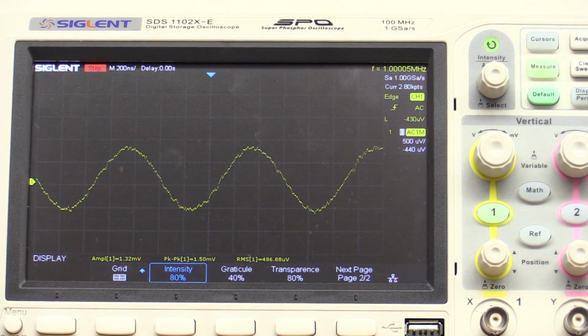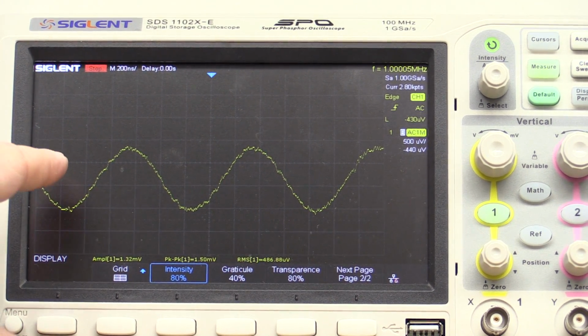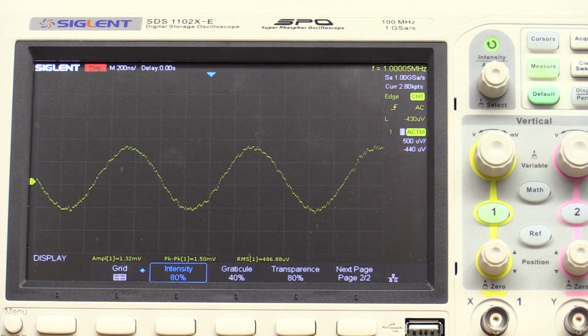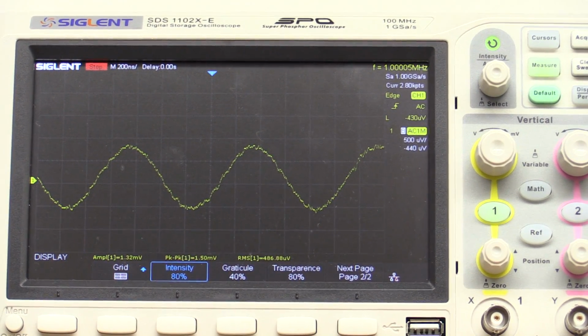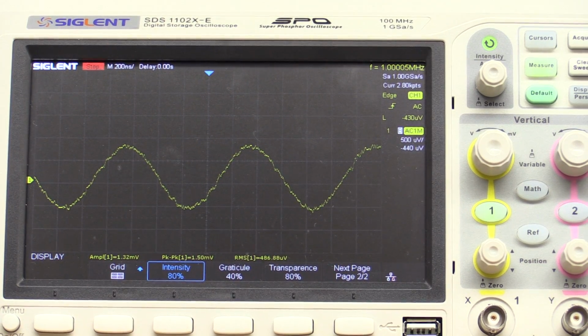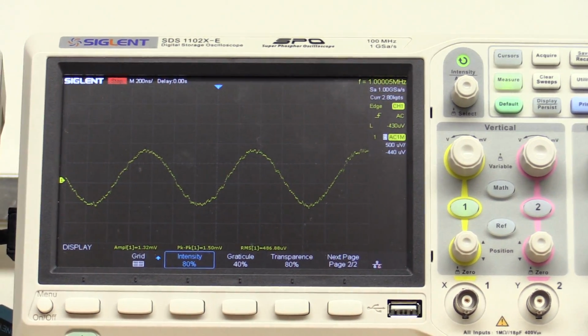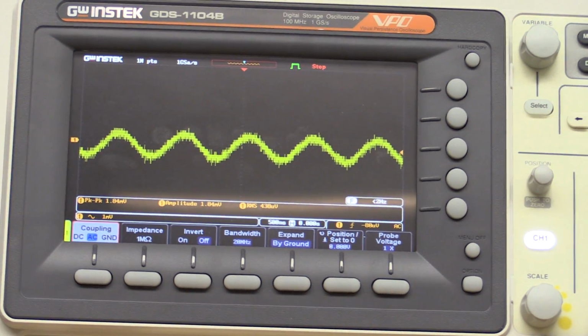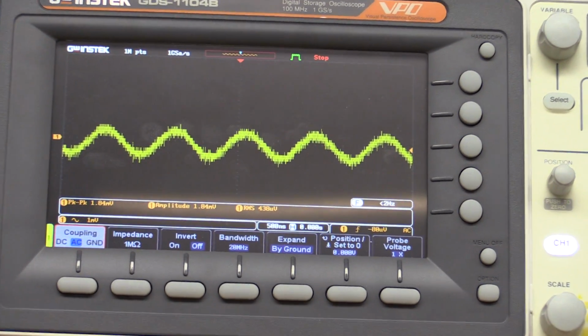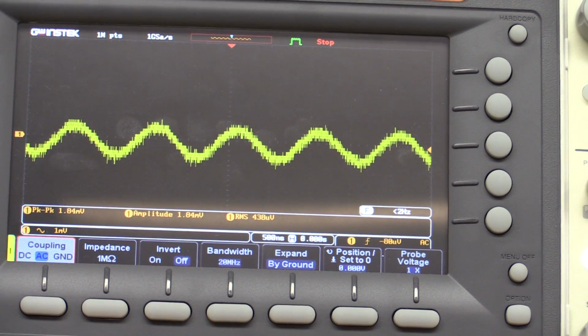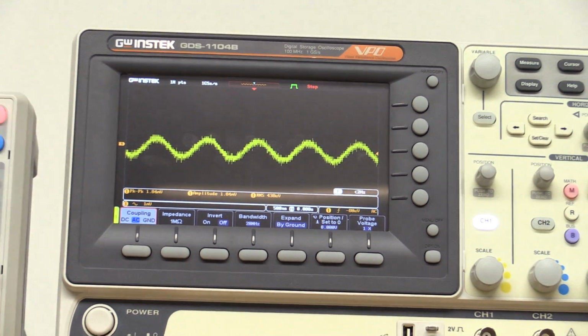And then the new Siglent 1000X series supposedly has a true 500 microvolt per division range, and it's a pretty good result. Fairly clean. Look at that. You can see some noisy details on there, but that's an excellent, excellent result for low noise measurement with a true 500 microvolt range. And then, this GW Instek, this is the worst of the bunch. Look at that. That's just horrid. Blech. Let's just not even go there.